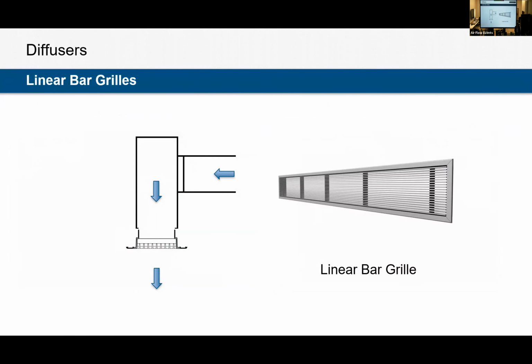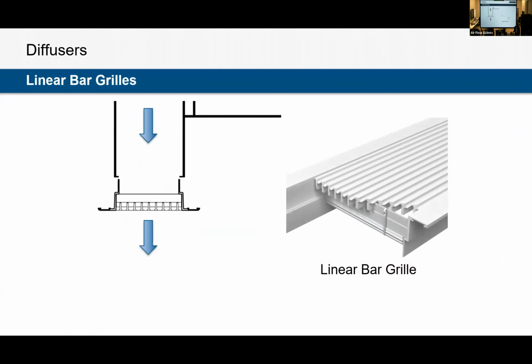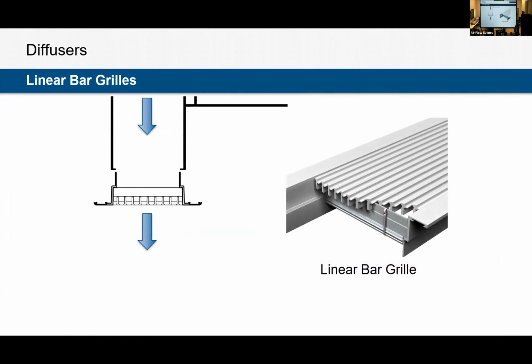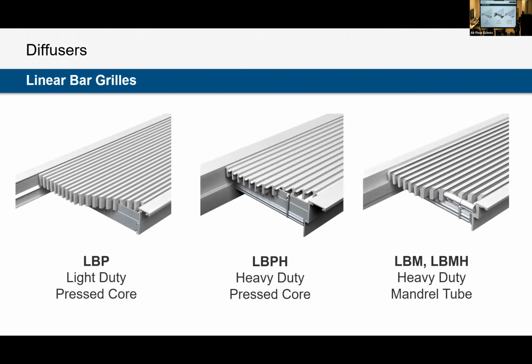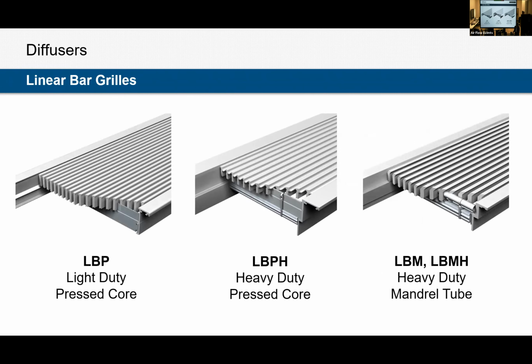Linear bar grills. Linear bar grills are usually used in two places, either sidewall, usually high sidewall grills, or on the floor. Similar to a slot, you're going to have the plenum behind it, but they are more visible, usually a little bit bigger, and have cores on the inside. So there's a light duty version and a heavy duty. Can anybody guess where you might use a light duty versus a heavy duty? Light duty on a pedestal, heavy duty on the floor. Perfect.